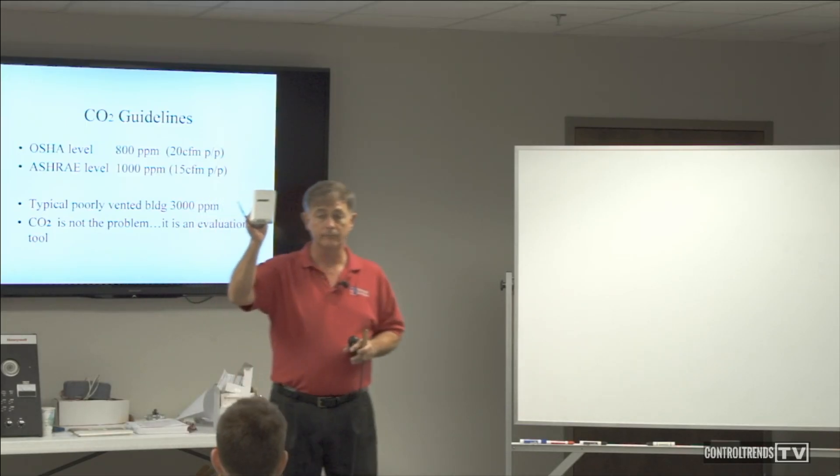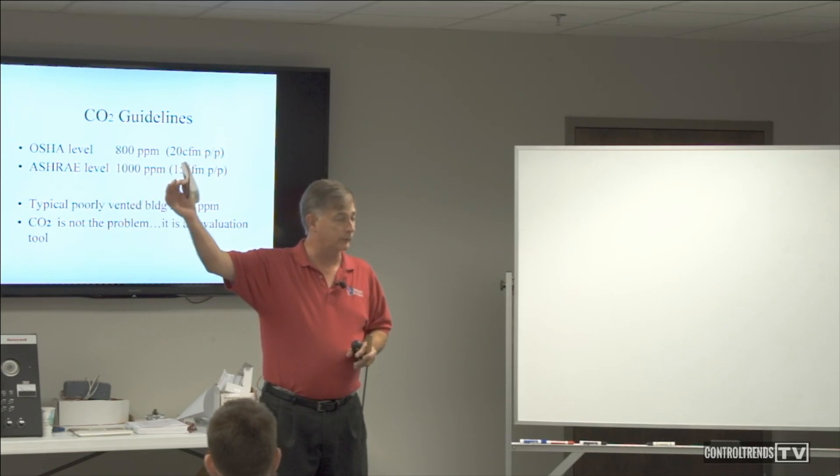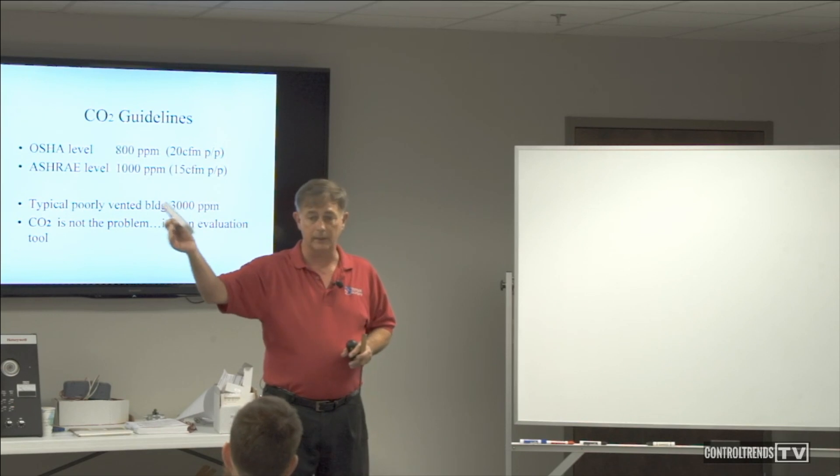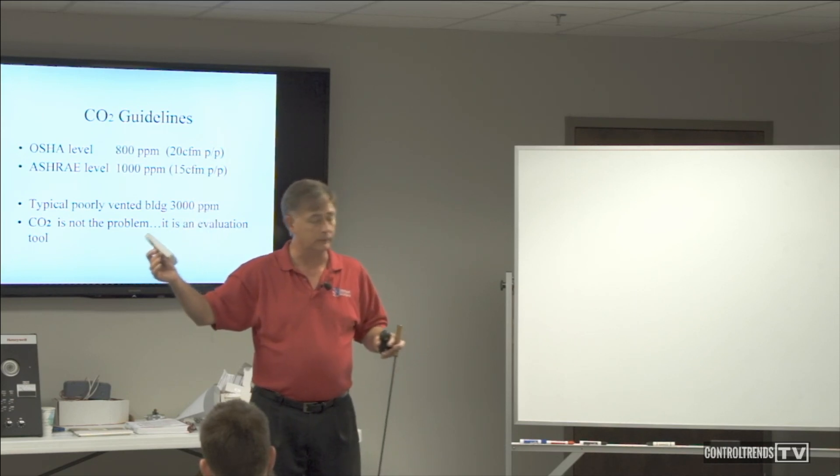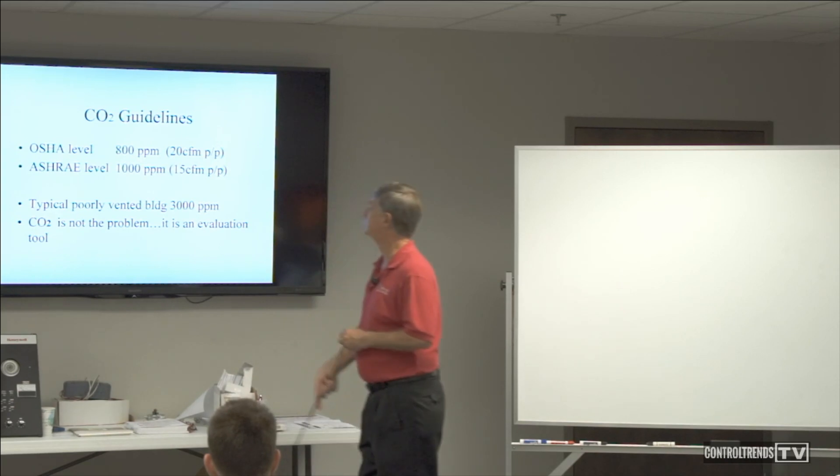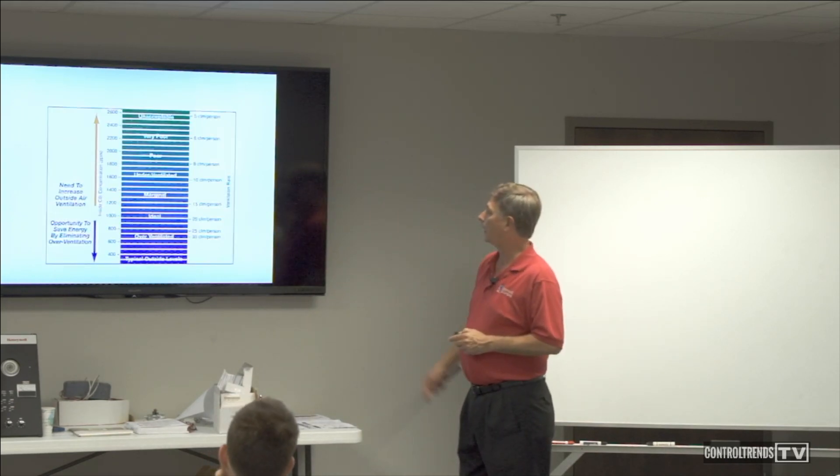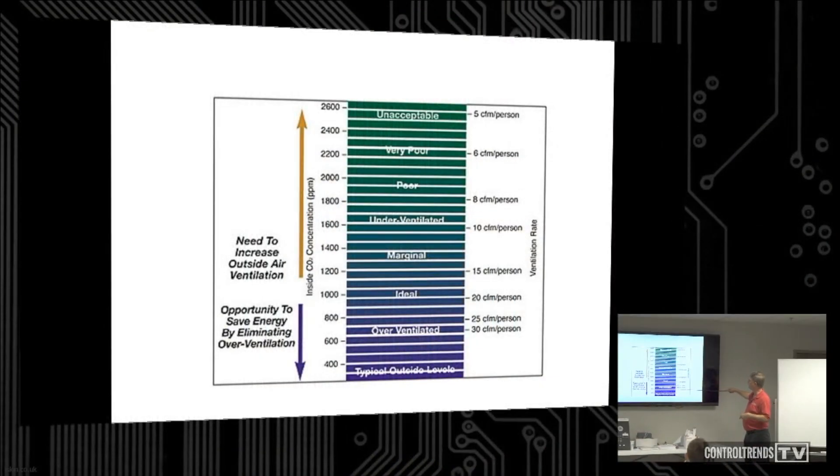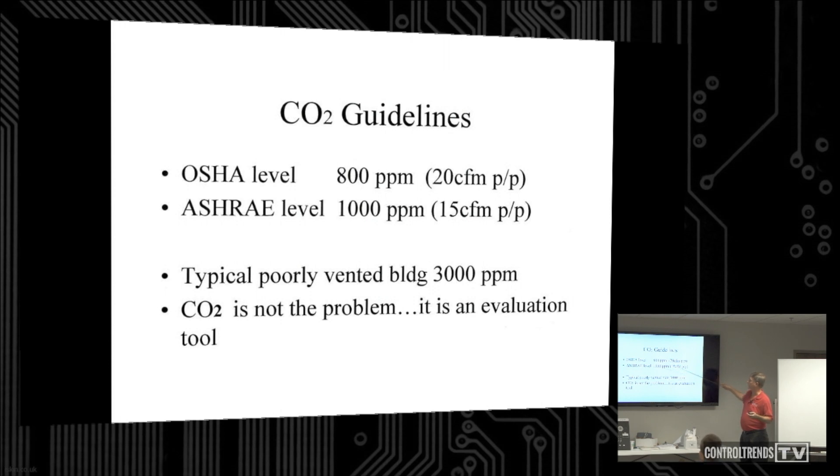CO2 sensors - integrate that with automation so the automation knows what the level is in this general area, and then we can respond accordingly to the system. If you have this in your handout, this is a good reference. We tend to hear a common term thrown around: we want to have about 20 CFM per person. If you equate that to your parts per million that we saw, 800 and 1,000, you see 800 is like 20 CFM, 1,000 is 15 CFM per person ventilation.